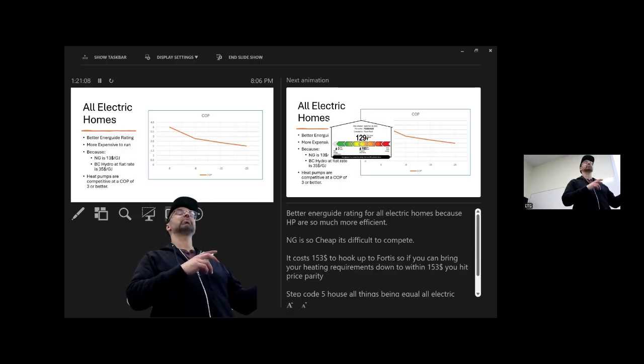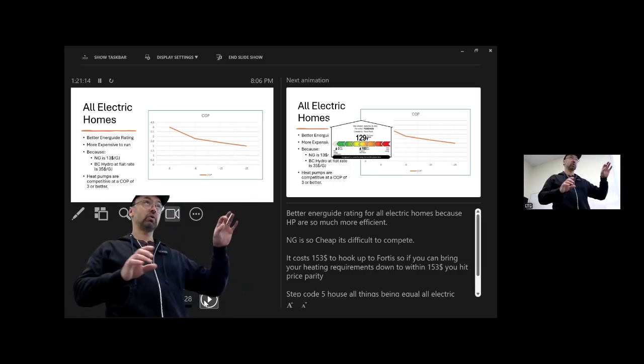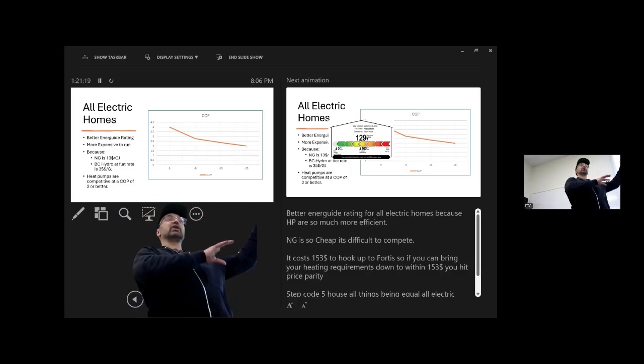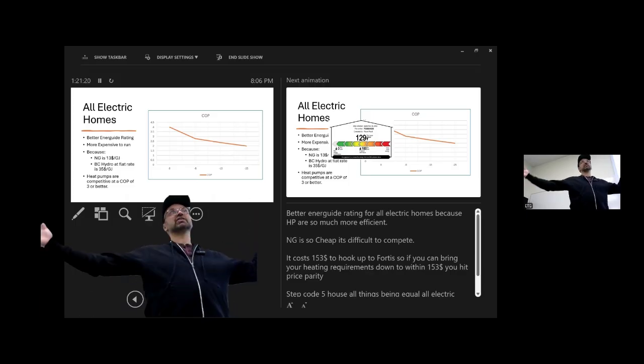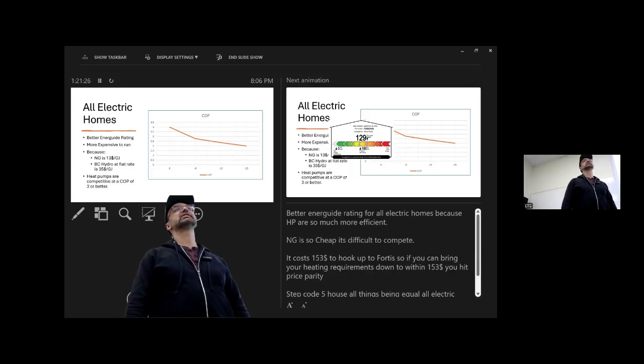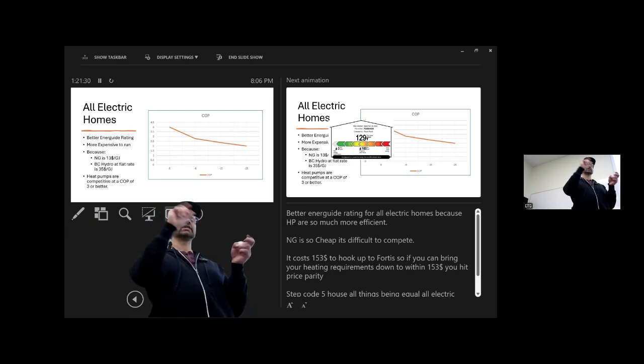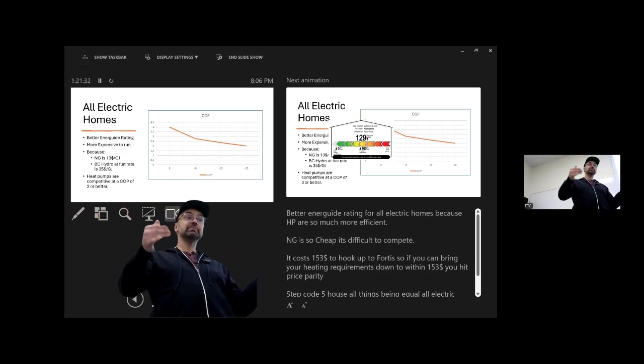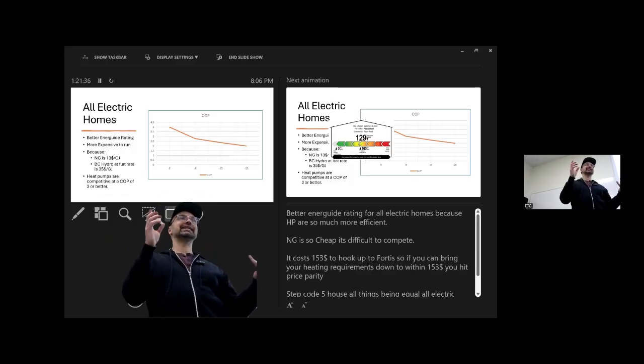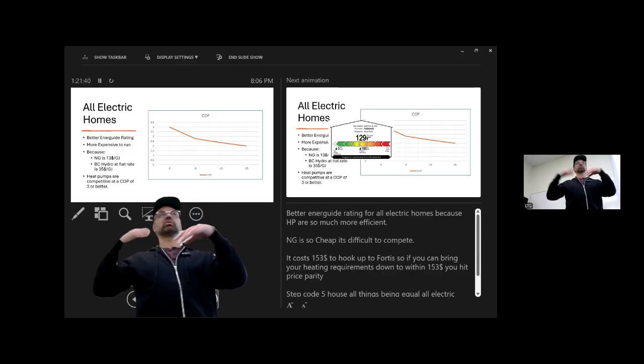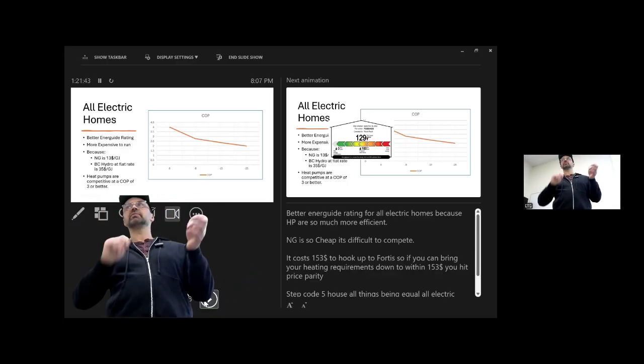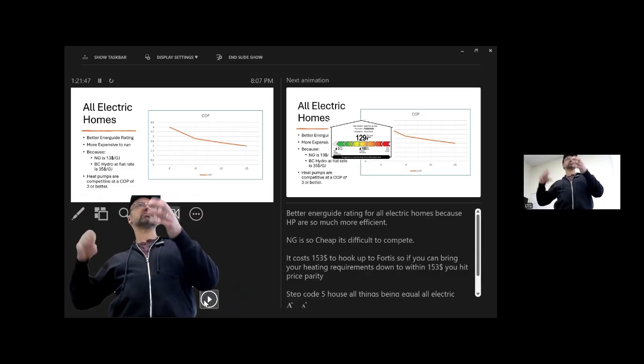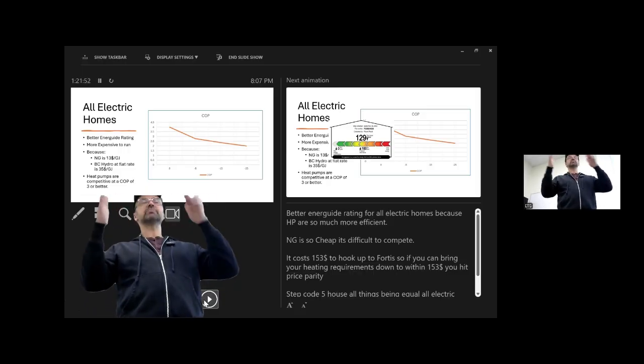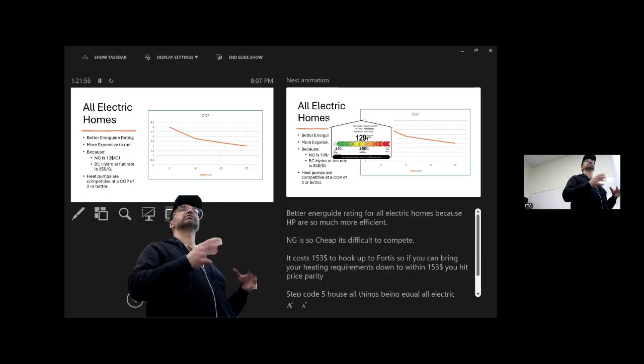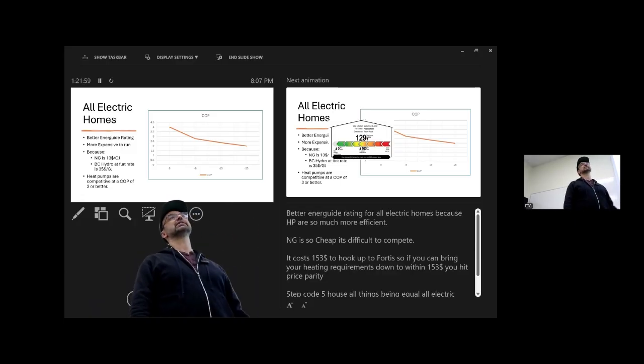So then you need to come up with some other heat. It'll be resistance heat or your furnace or all of those kinds of things. And if you were going to size it so that your heat pump put out 50,000 BTUs at minus 33, then you have this enormous system, or multiple systems, which causes problems. If you have a 100,000 BTU heat pump, when it's minus 2 and you only need 10,000, it's whirling up to get going, and then it meets your energy demand and shuts down, and then goes on and shuts down. So for heat pumps, you don't size them to the lowest temperature. You size it so that you're always going to be relying on resistance heat to make up the difference.